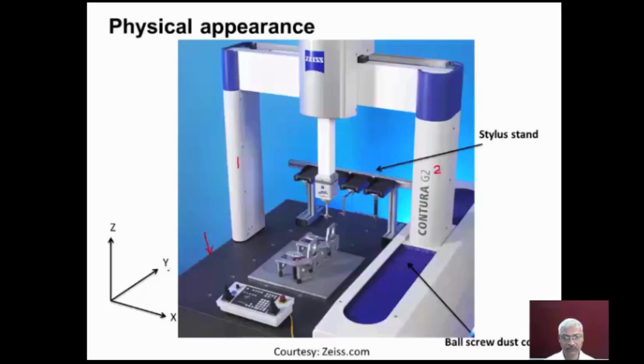These two columns move along the y-axis by using the ball screw and appropriate drives. You can see there is a dust cover to cover the ball screw so that dust will not accumulate on the lead screw. At this place, column number 1 will be moving on the granite surface. There will be air jets below this column surface so that it moves frictionlessly. Between these two columns, there is a bridge, and this bridge carries the probe head, and we can mount different kinds of probes to this probe head. This probe head can move vertically up and down in the z-axis by using the appropriate drive system.